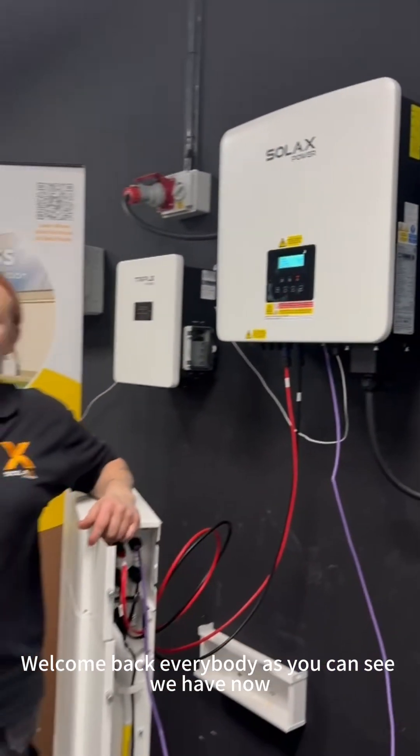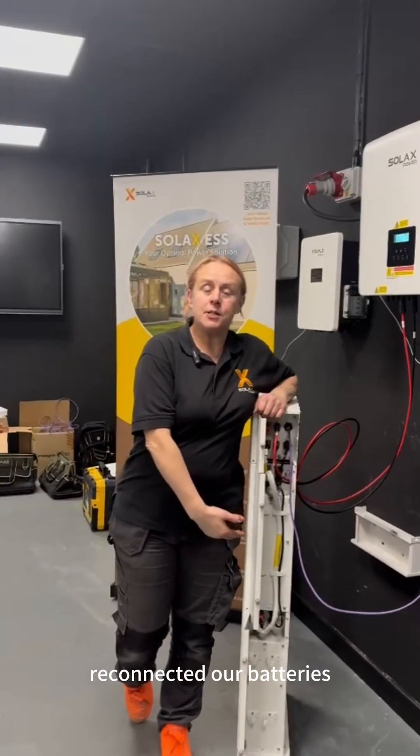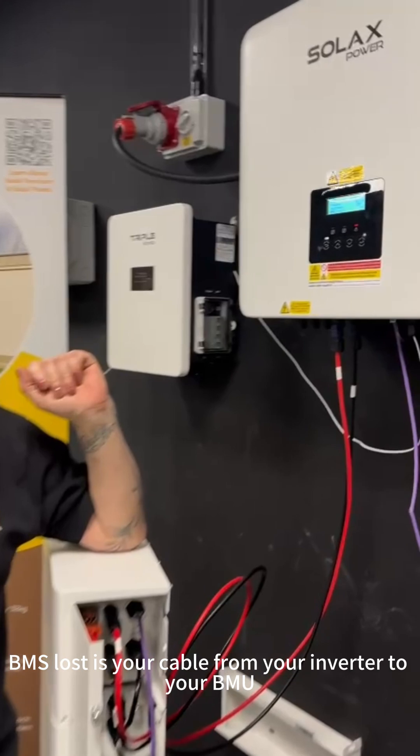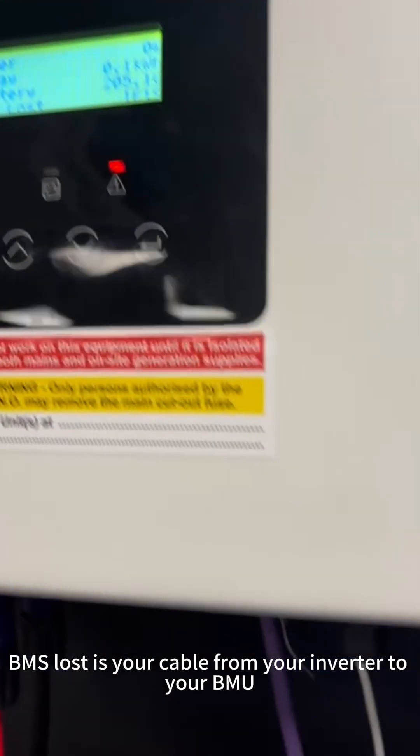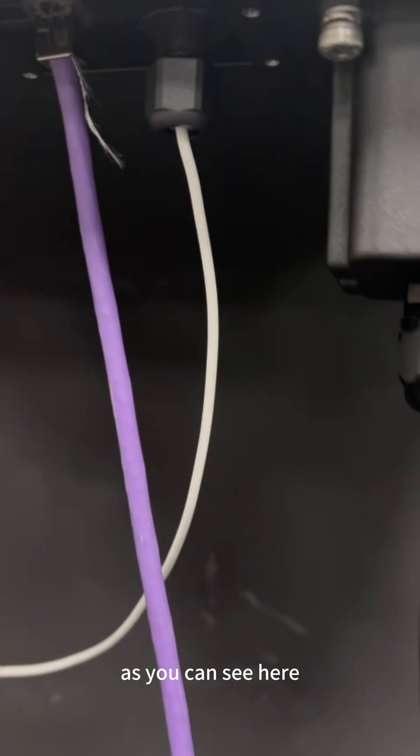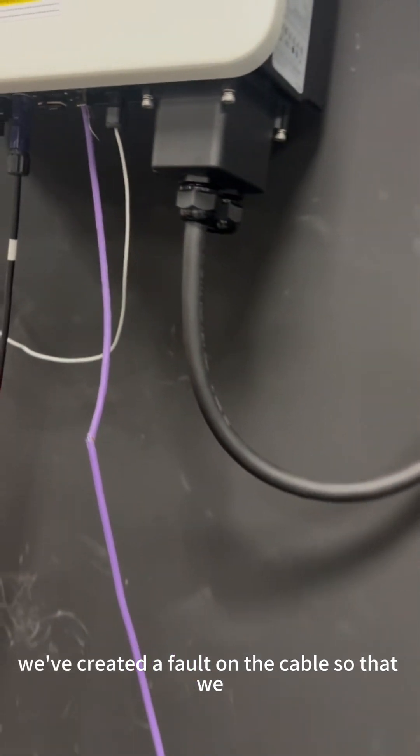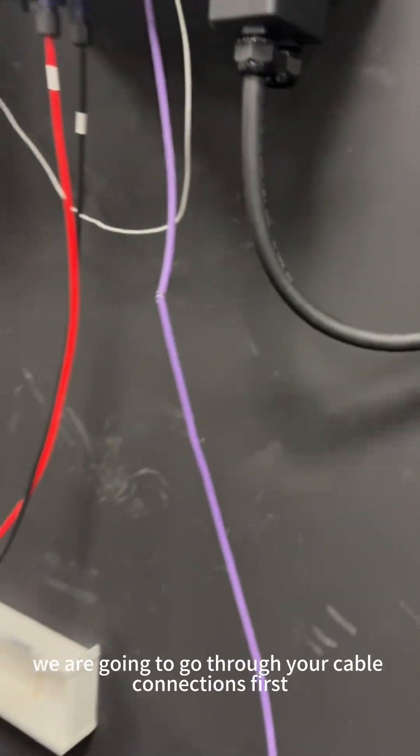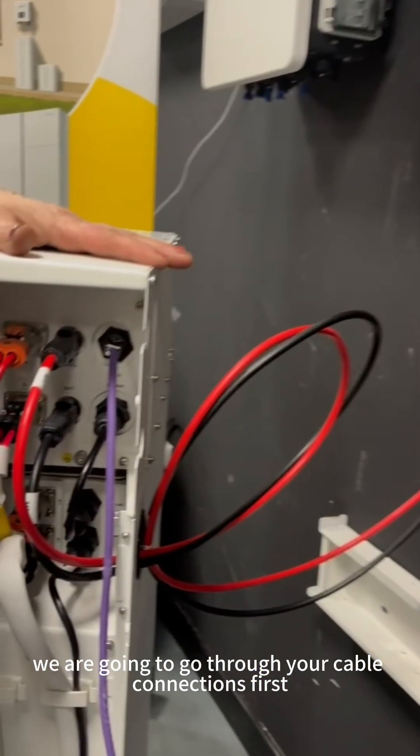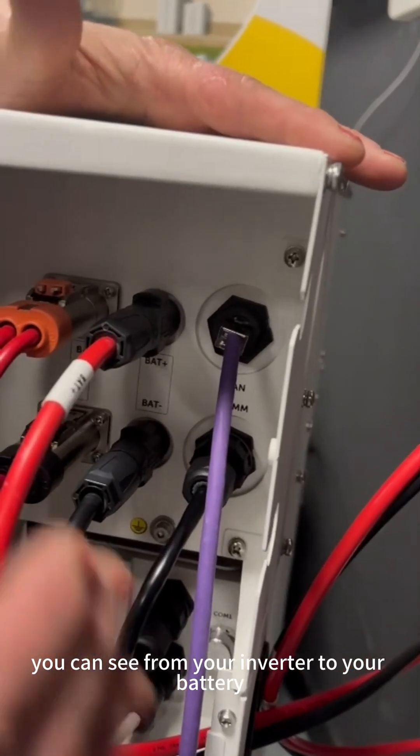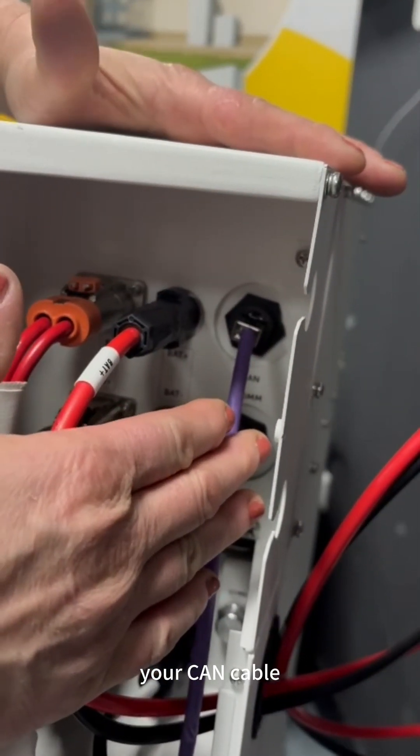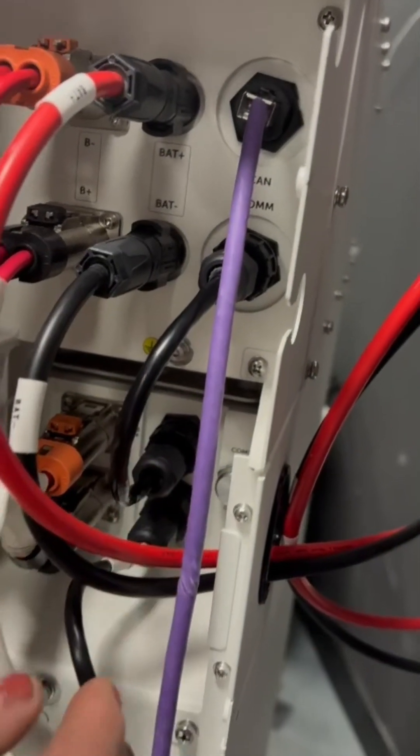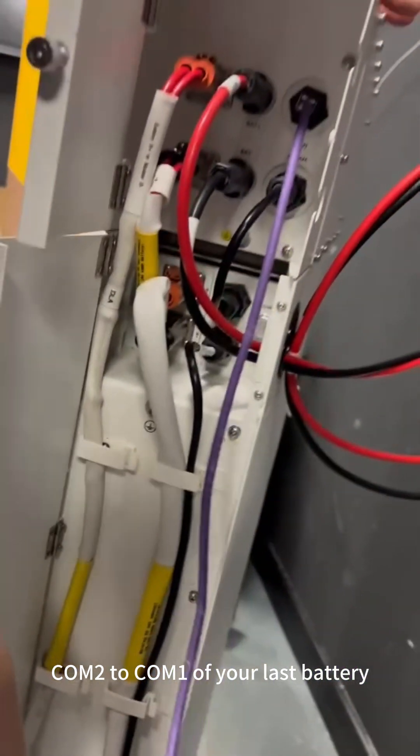Welcome back, everybody. As you can see, we have now reconnected our batteries and we've gone into BMS lost mode. BMS lost is your cable from your inverter to your BMU. As you can see here, we've created a fault on the cable so that we can recreate this fault to show you how to rectify it. We are going to go through your cable connections first. You can see from your inverter to your battery, your CAN cable. Then you go from your comms cable to your COM1, COM2 to COM1 of your last battery.